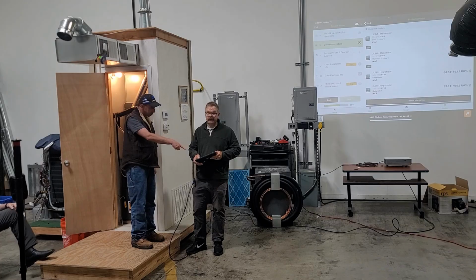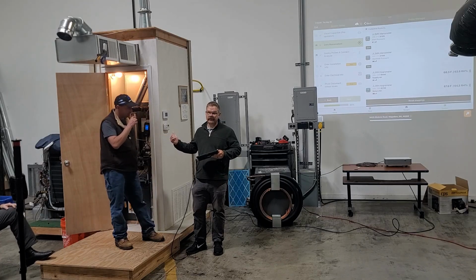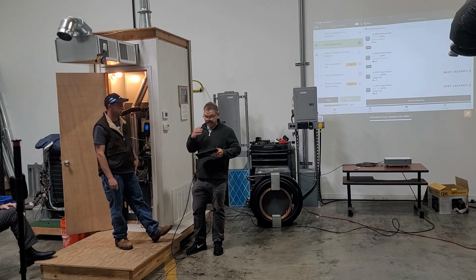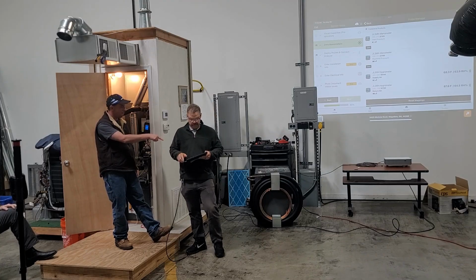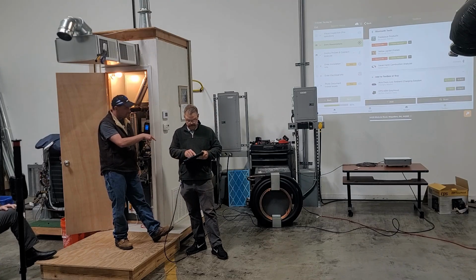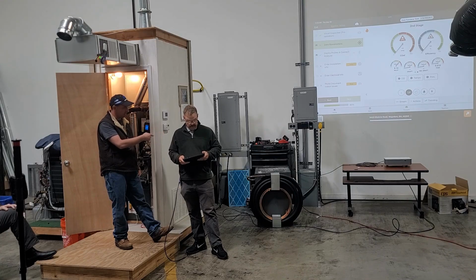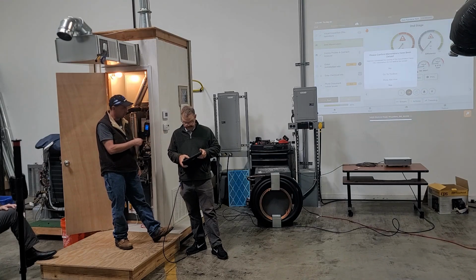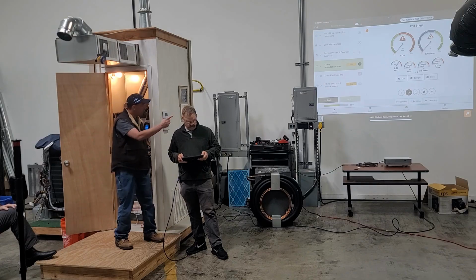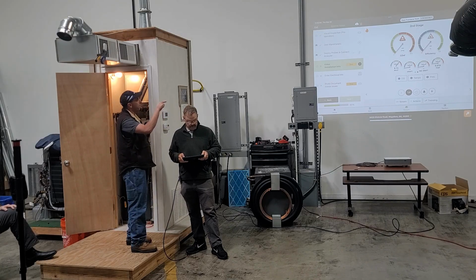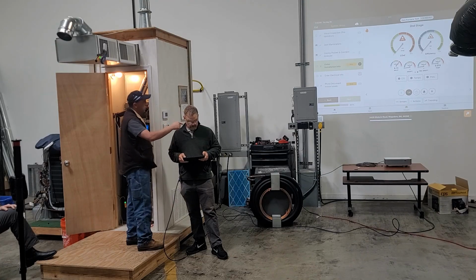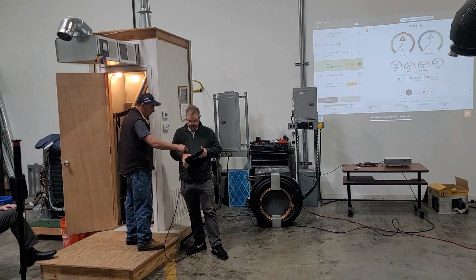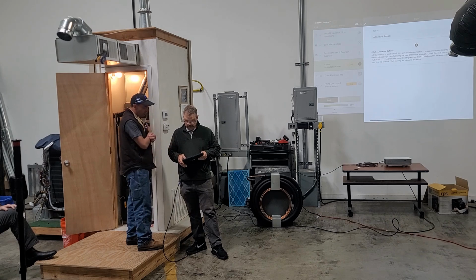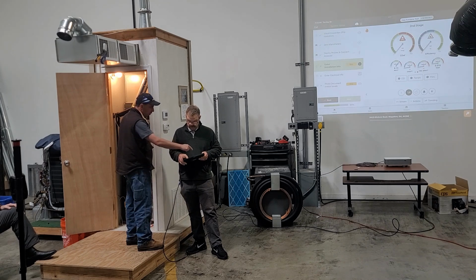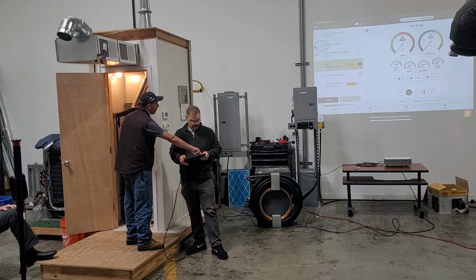We're not gonna zero the 165 because we're already monitoring the inlet gas pressure. So go back, manometers are zero, so zero manometers, yes, already been done. Deploy probe, and here's another thing, everything in here is a button. If you have any questions on anything, call me. But also, you can click on the gauge and see what the target is supposed to be, what the allowable ranges are. And if you want to know where to put your probes, there's a little icon.